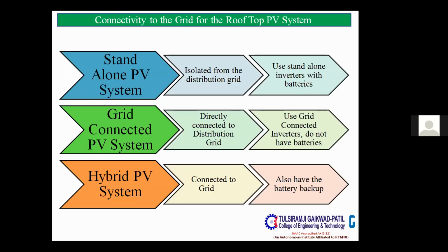Then if we talk about the connectivity of the rooftop PV system, we have three schemes available with us. The first one is the standalone PV system. The second one is the grid connected PV system. And the third one is the hybrid kind of system, wherein we will have battery backup arrangements. In a standalone system, our system has standalone inverters with batteries. It is not connected to the distribution grid, or in other words, it is isolated from the distribution grid. In case of the grid connected PV system, it's directly connected to the distribution grid, and it uses inverters. It doesn't have any batteries.